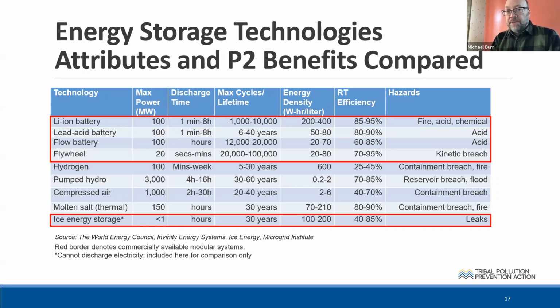But also it's just how long does it last. If you're using that battery every day in a daily charge-discharge cycle, lithium batteries degrade fast—so 6 to 8 years is about all you're going to get. Some manufacturers might argue with me, but generally 6 to 8 years, maybe 10, is what you'll get out of a lithium energy storage system cycled daily. So if you're planning a project with a 20-year cost-benefit analysis, you have to figure on replacing those batteries in 8 or 10 years.